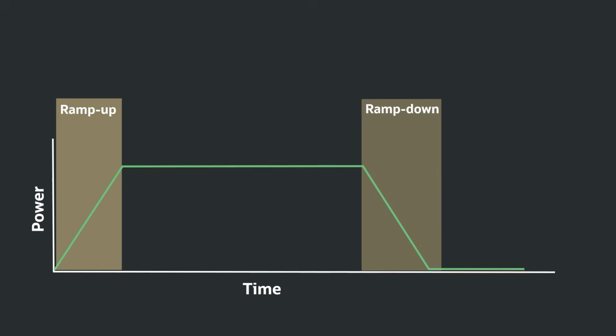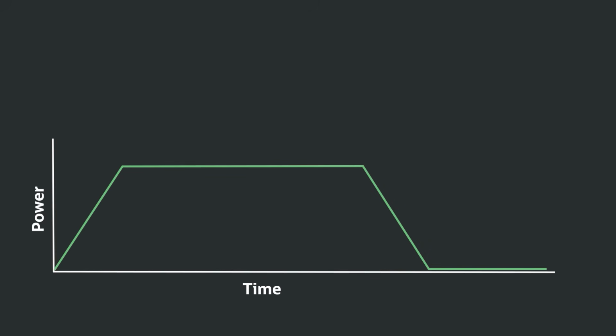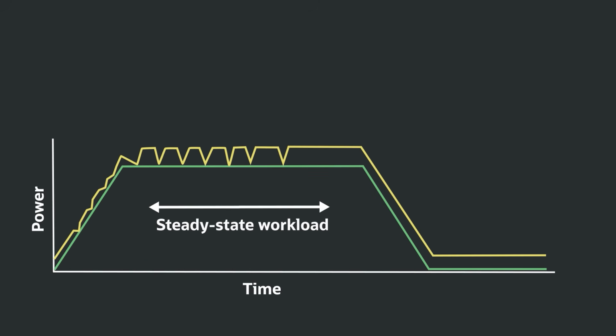The second tool in our tool chest is from the GPU and AI accelerator chip vendors. They provide functionality that lets you slowly ramp up, you can set a rate like 1% or 0.5%, so it slowly ramps up the GPU power instead of going up instantaneously. The same applies coming down, it can slowly bring the GPU power down instead of going straight from 100% to 30%. In addition, vendors provide functionality to set a minimum floor so that while the workload is running, it doesn't come down below 90 or 80%. That's the second tool in our tool chest.